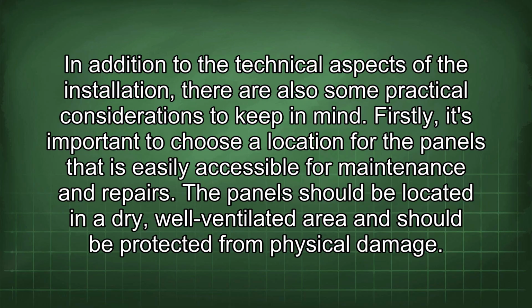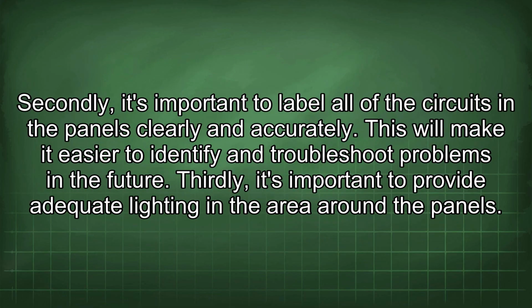In addition to the technical aspects of the installation, there are also some practical considerations to keep in mind. Firstly, it's important to choose a location for the panels that is easily accessible for maintenance and repairs. The panel should be located in a dry, well-ventilated area and should be protected from physical damage. Secondly, it's important to label all of the circuits in the panels clearly and accurately. This will make it easier to identify and troubleshoot problems in the future.